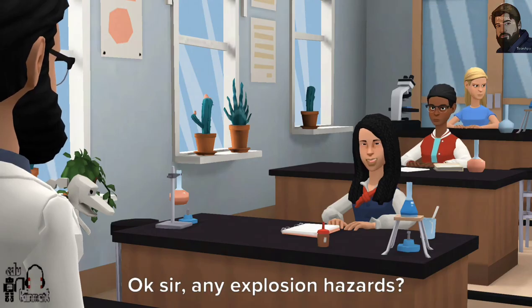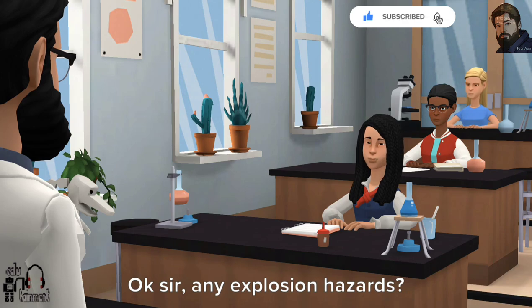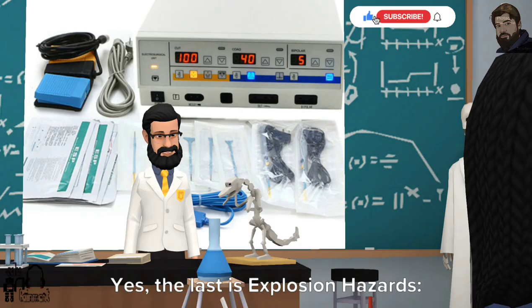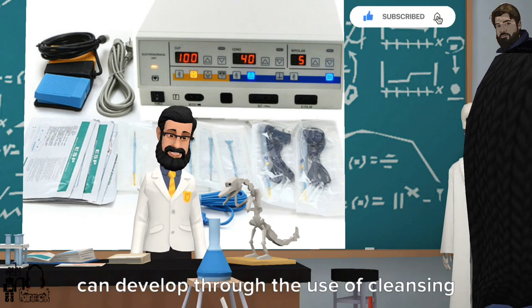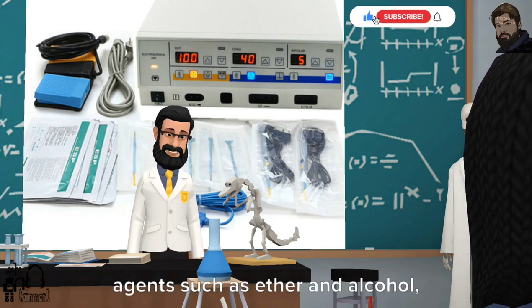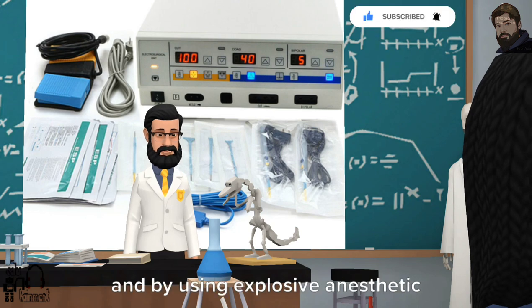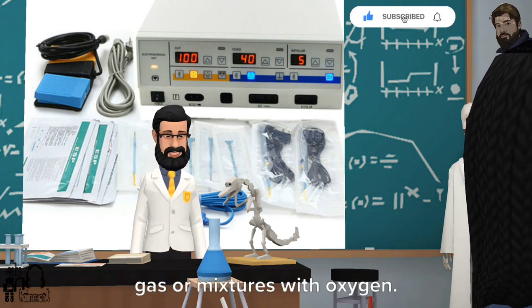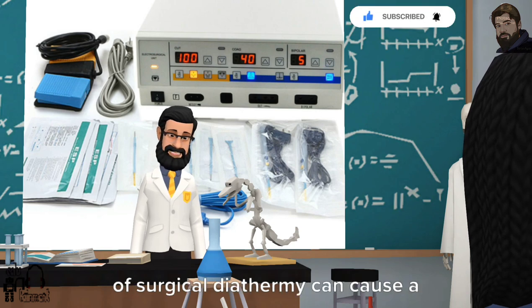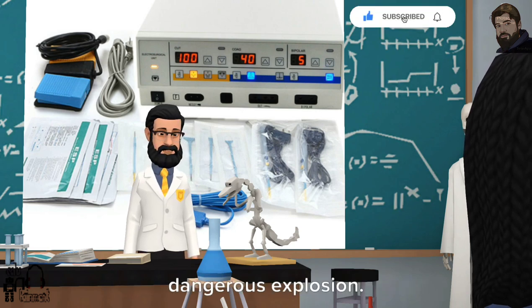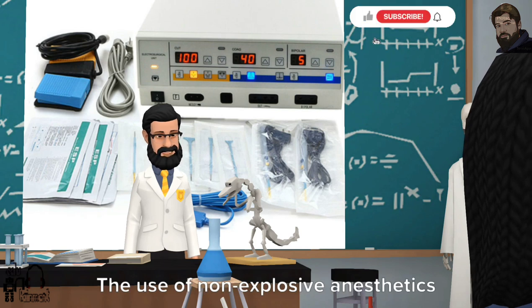Okay sir, any explosion hazards? Yes, the last is explosion hazards. In operating theatres, danger zones can develop through the use of cleansing agents such as ether and alcohol, and by using explosive anesthetic gas or mixtures with oxygen. The sparks associated with the use of surgical diathermy can cause a dangerous explosion.